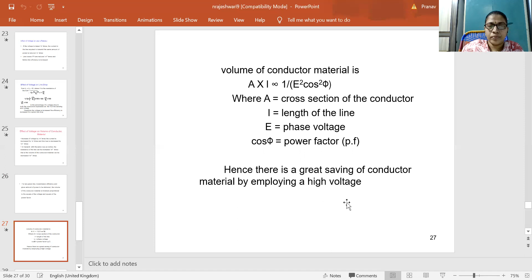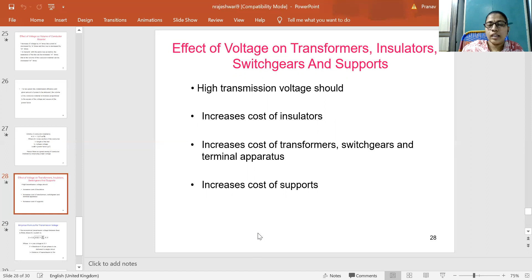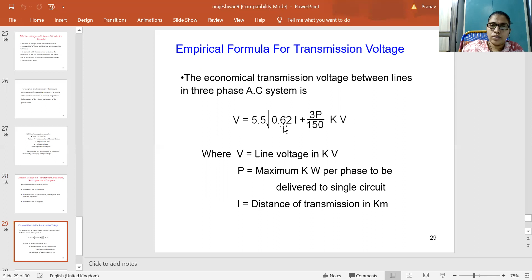And coming to the effect of voltage on transformers and all the equipment used in transmission systems, if voltage is increased, the transformer cost also increases, the cost of insulators used in these transmission systems also increases, and the cost of the supports used for transmission also increases with higher transmission voltages. So this is the formula for transmission voltage: V equals 5.5 times the square root of (0.62 I plus 3P by 150) kilovolts.